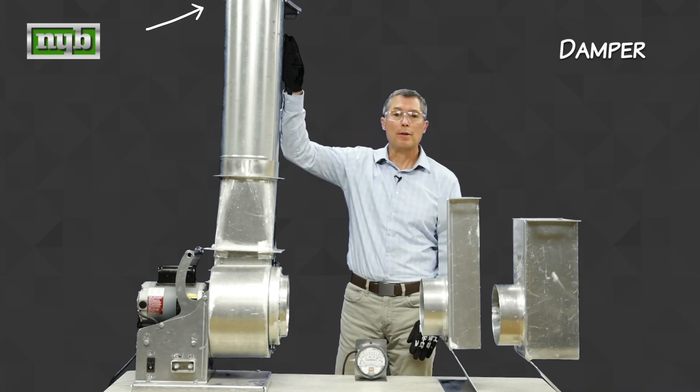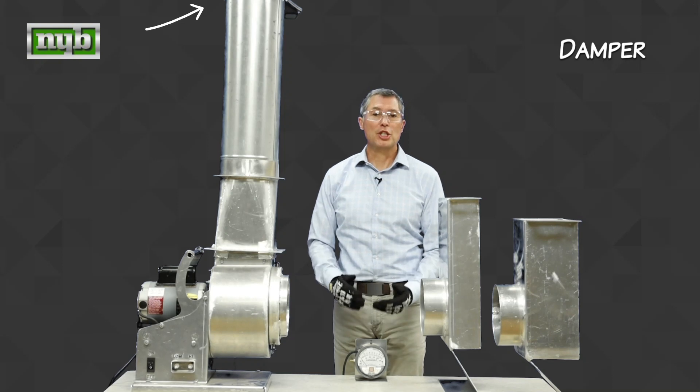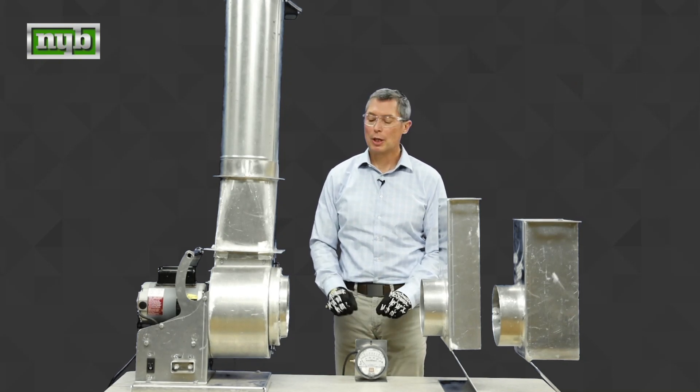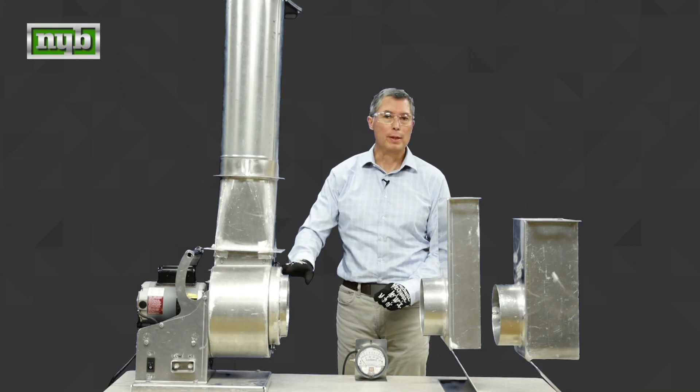We have an outlet damper on the fan. Outlet damper is set to generate about one inch of resistance or 250 Pascal on our gauge. That will be our benchmark setting for the fan with the open inlet.